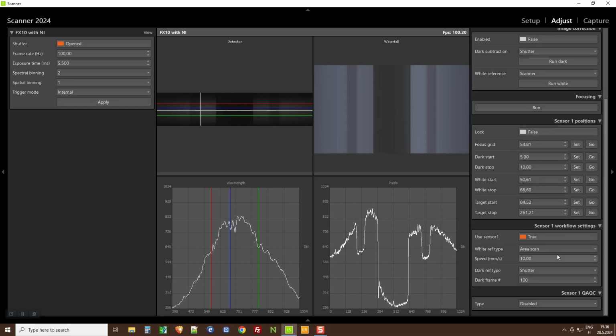And here I will set up the system. So indeed, I want to record the white area and also to take the dark reference. Notice that for the white reference data acquisition, you have the possibility to either not take it, to always take a certain amount of frames in the white start position, to make a scan between white start and white stop, and also you can make it manually by putting yourself a white reference under the camera.